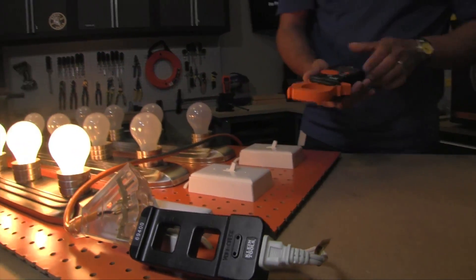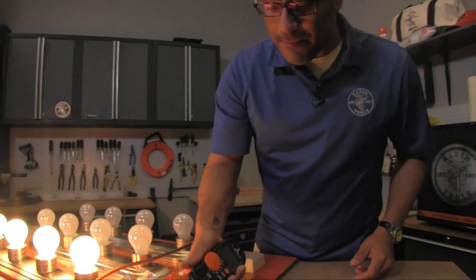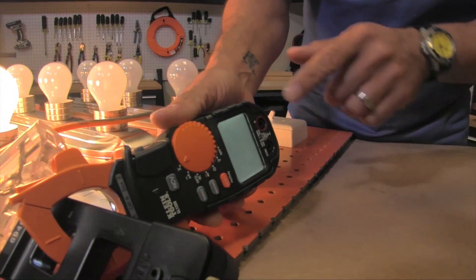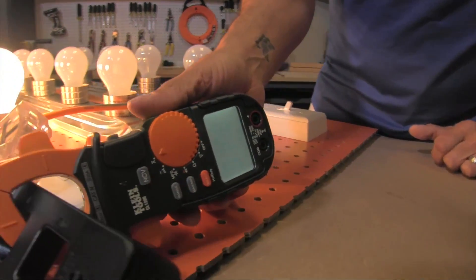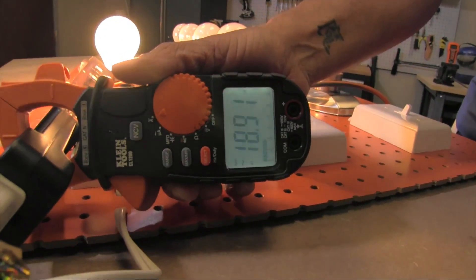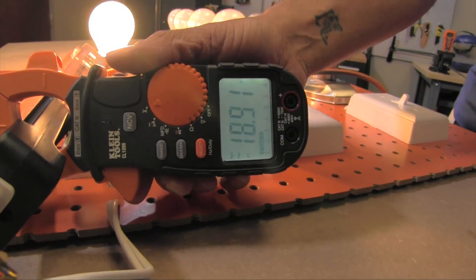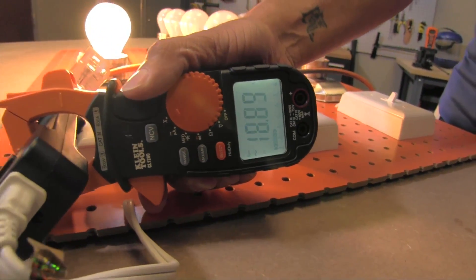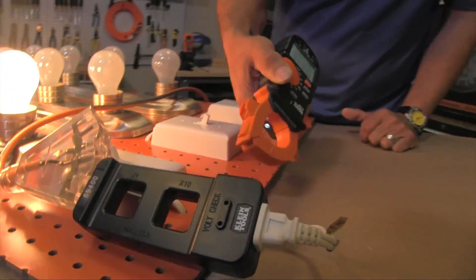So for example, if I clamp on right now with these lights on, you'll see that I'm pulling 1.78 amps. Right now if I were to move this to the times ten, it goes up to 18.9, so basically just multiplying the signal times ten to give you a little bit better resolution.